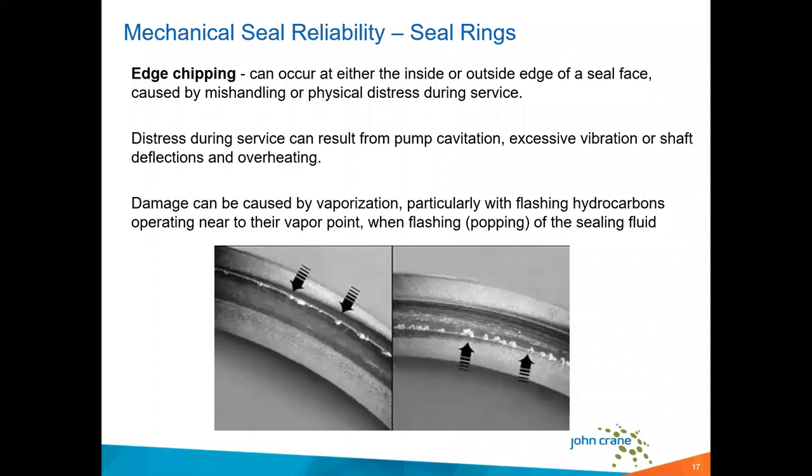Some examples here of edge chipping, and these would be the areas we would look at in terms of clues as to what occurred or what's potentially contributing to the reduced performance of the seal. So the edge chipping can occur either at the inside or outside edge of the seal face, usually caused by some kind of physical distress during service.